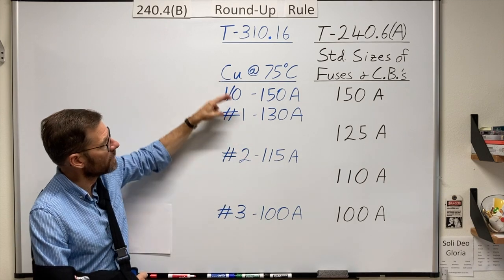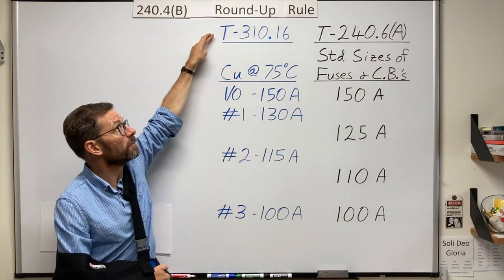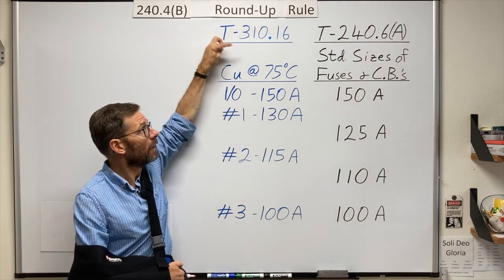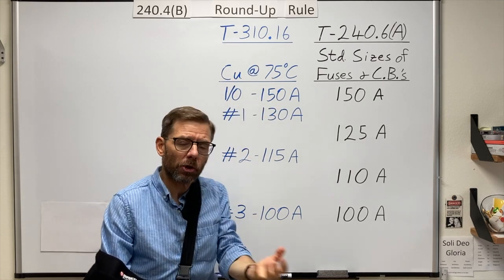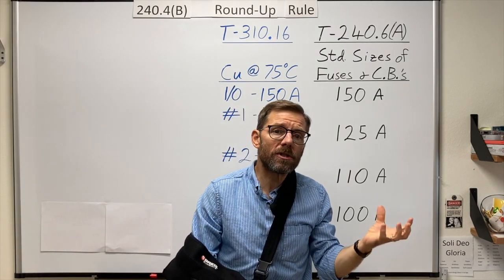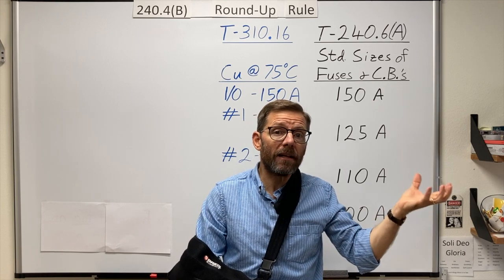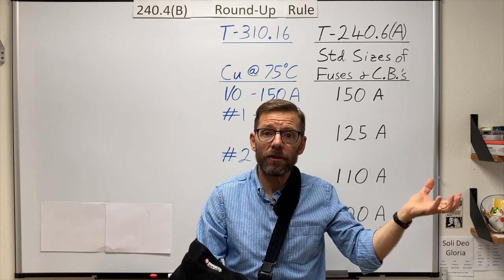Here I have some ampacities of copper conductors from Table 310.16, and I pick the 75 degree Celsius rating because in our commercial and industrial work, most of our newer equipment is rated for at least 75 degrees.